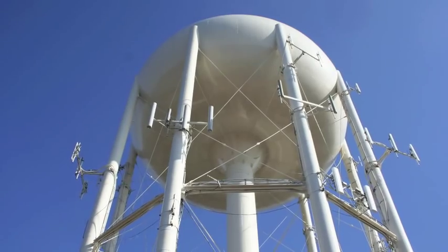This is Ron Perrin. What you've been looking at is about 2.5 feet of sediment in a 1 million gallon ground tank out in West Texas. After we inspected it, the utility realized how much sediment was in there and they contracted us to go in and remove the sediment. This was mainly white sand, but all sediment is not this nice.